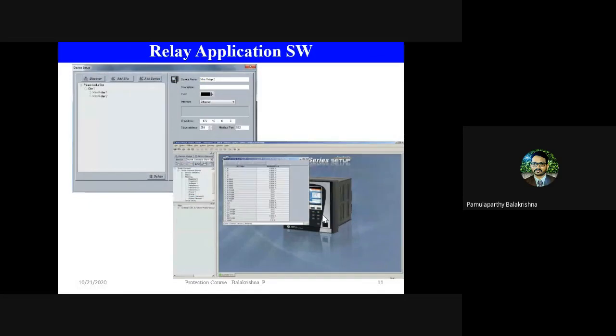Okay, so each digital protection relay comes with its own relay application software, where the operator connects to the digital relay by giving its IP address. So if the relay has Ethernet communication, and you know the IP address of the relay, you configure that IP address here and then connect to the relay. Once you connect to the relay, it will automatically display the different inputs that are coming, the different protection functions that are executing, and the different control commands and events. You can navigate all those things in the menu here.